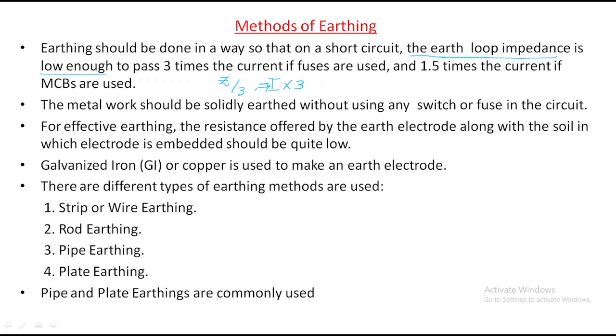Understand? And 1.5 times if an MCB is used, then the impedance must be less, and 1.5 times the current will flow. So we are decreasing the impedance. What happens when we decrease the impedance? Look here. It is connected to ground. This is the earthing. Earth loop impedance means the impedance between this point and this ground point. This will be low. Whenever it is low, the current won't flow like this; the current will enter like this from the metal body. That is the process we are using here. Whenever impedance is decreased, automatically the current increases.